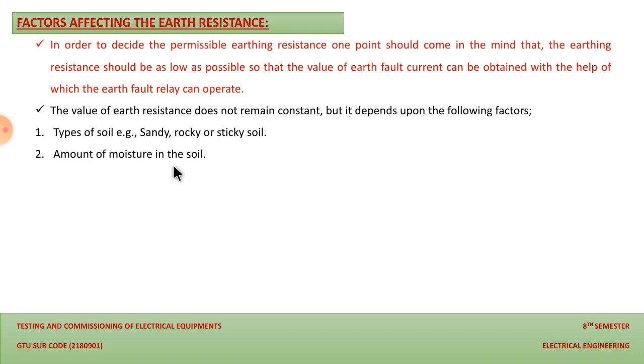And the second factor is the amount of moisture in the soil. This is the most important point according to the type of soil that we have already discussed in the first point. And the next is the temperature of the soil. This is again a main factor. If the temperature of the soil is more, then the soil is not moist. And if the temperature of the soil is less, then if we add moisture inside the soil, it will remain moist for a long time. And if the temperature of the soil is more, then we have to pay more attention to the moisture of that portion where we have provided our earth electrode.